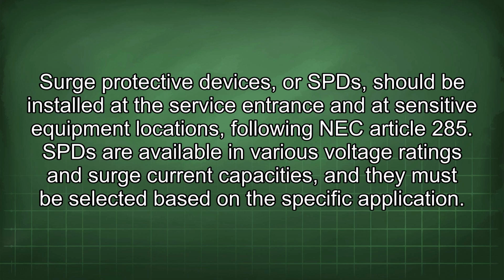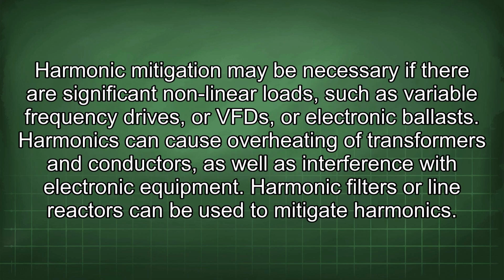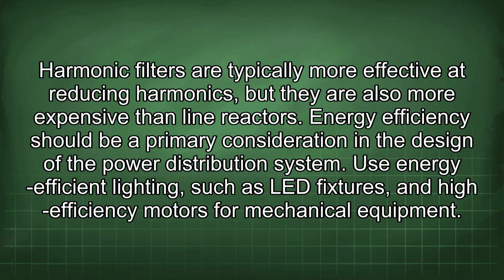on the specific application. Harmonic mitigation may be necessary if there are significant nonlinear loads such as variable frequency drives, or VFDs, or electronic ballasts. Harmonics can cause overheating of transformers and conductors, as well as interference with electronic equipment. Harmonic filters or line reactors can be used to mitigate harmonics. Harmonic filters are typically more effective at reducing harmonics, but they are also more expensive than line reactors.